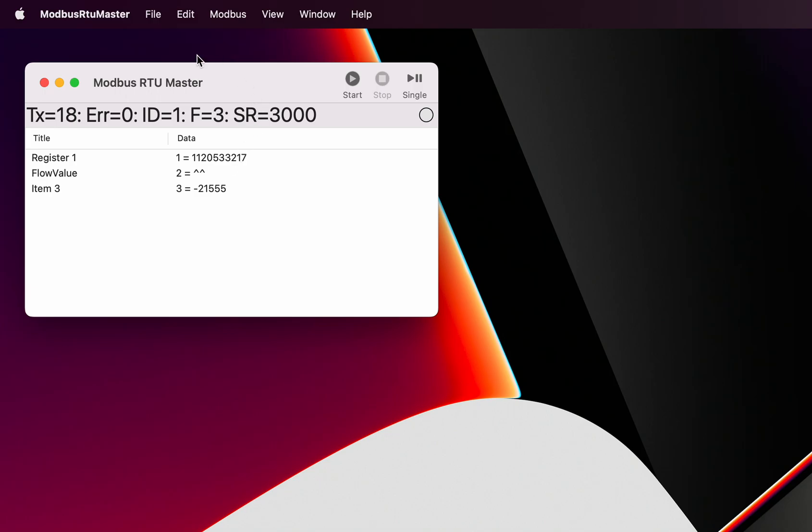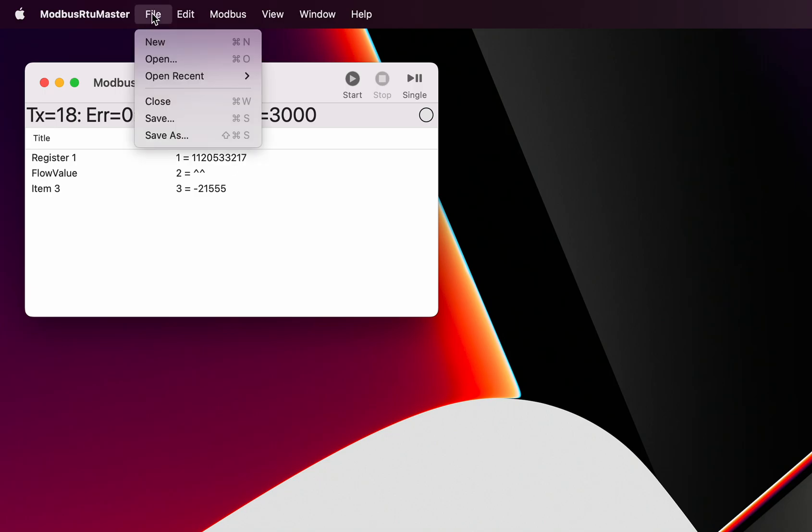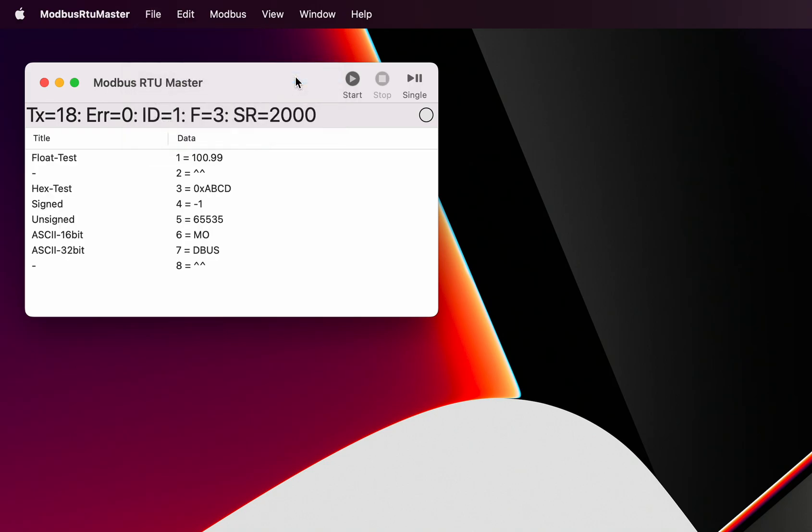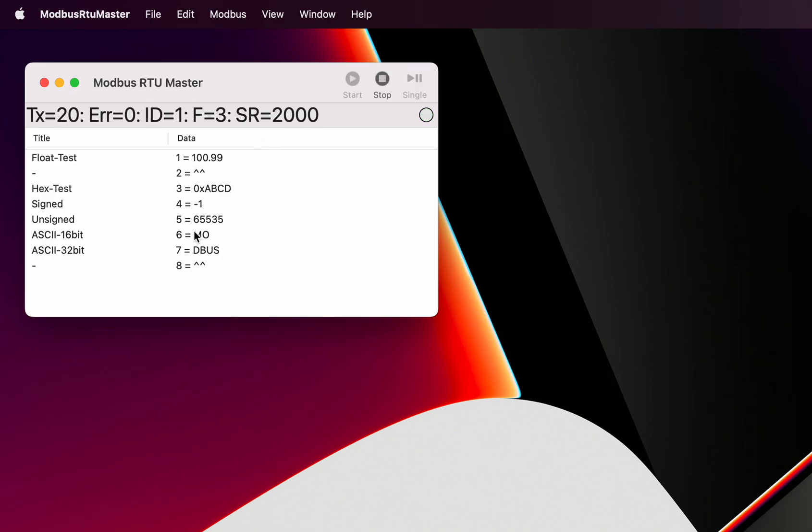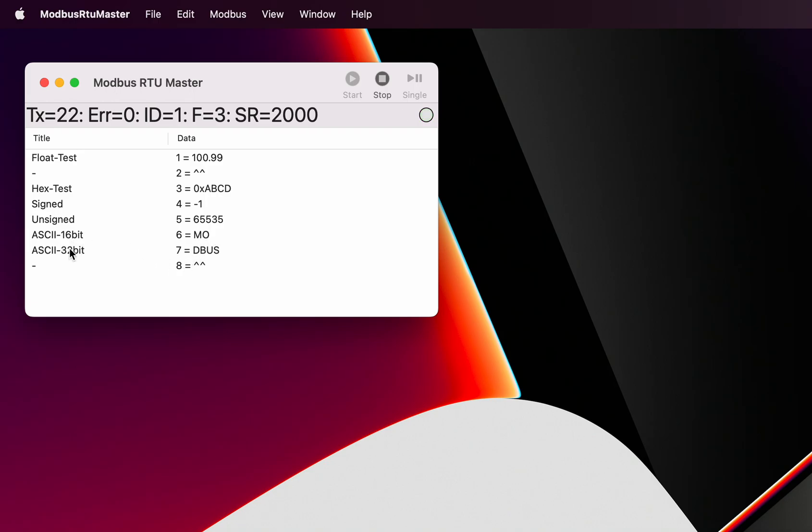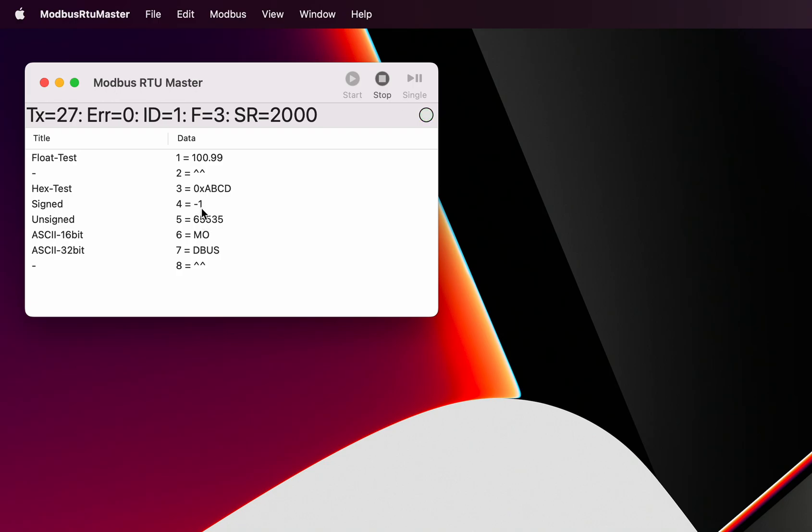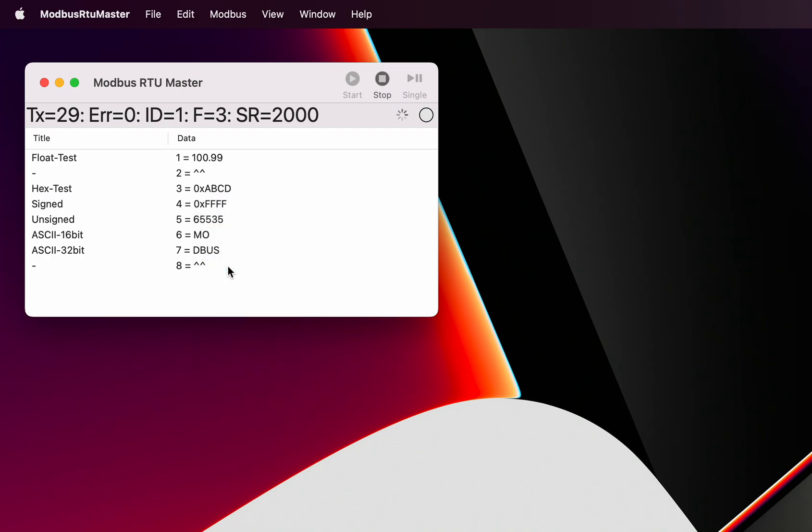For a bit more of a demonstration of that, I've got a demonstration file prepared. Here's a demonstration file which shows a number of those options, a number of interpretations. For example, here we've got an ASCII interpretation of one register and then two registers together. Here we have got a signed and an unsigned interpretation of a register, so the difference between the two. We can change it to hexadecimal and then we can see what that looks like in hexadecimal, or we can switch it back to decimal. Decimal by nature is a signed decimal.